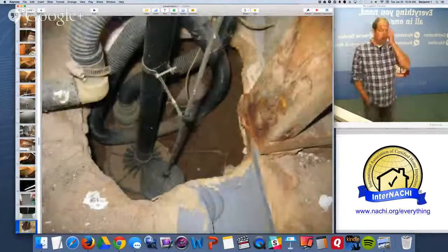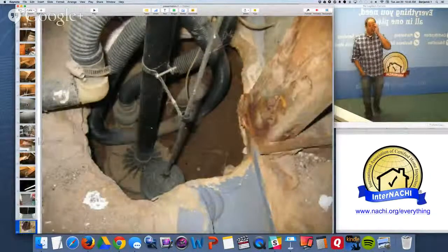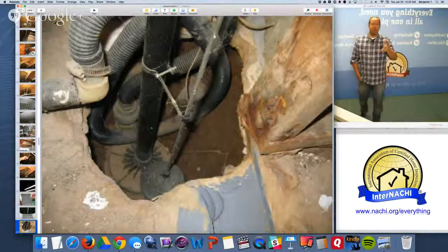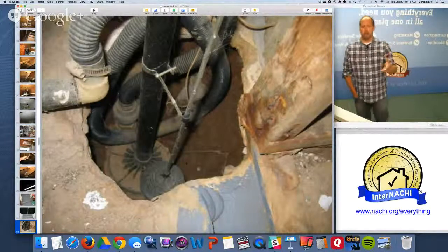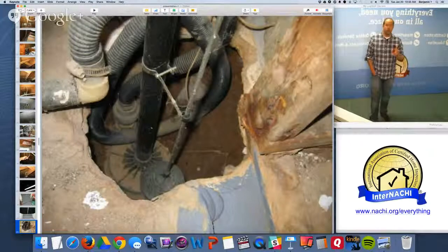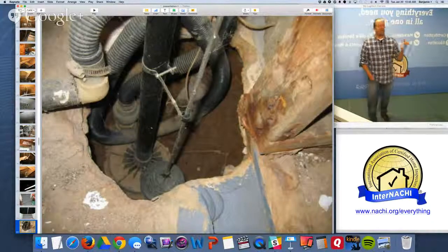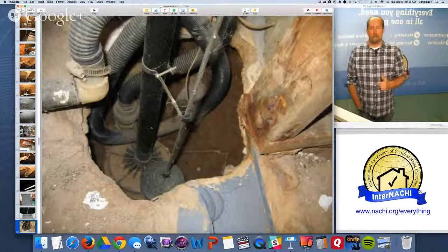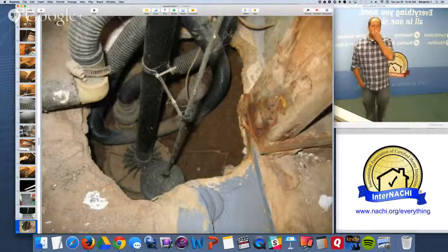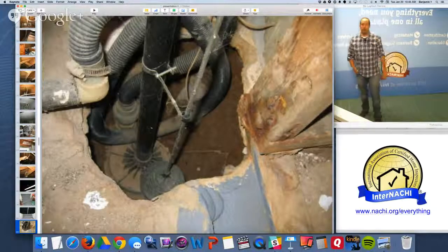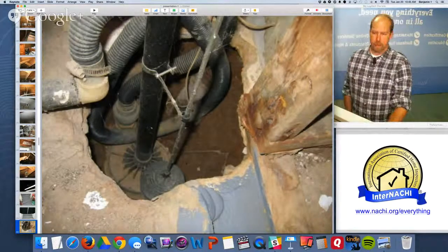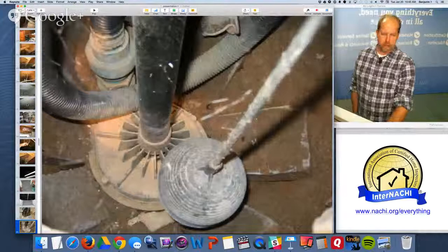There's a sump pump. This home has indications of water intrusion and they have a sump pump, but it's not professionally installed — poor workmanship. This pump is going to fail prematurely because it's sitting in mud and it's going to suck all that mud up. It should be in a sump pump bucket. It takes a lot of effort to install one of these properly, but when you need it, it needs to work reliably. This pump is unreliable. It needs to be replaced and reinstalled professionally.